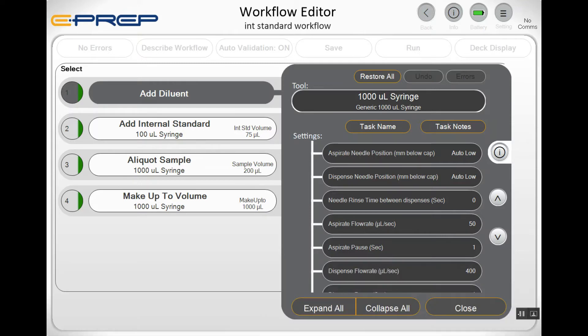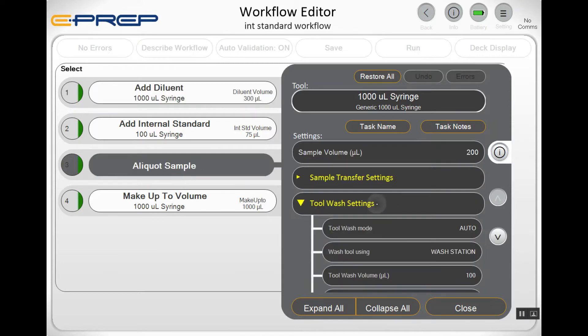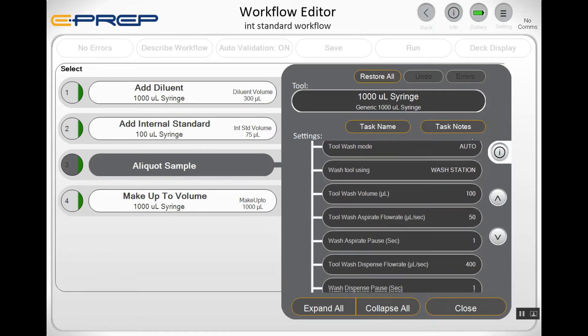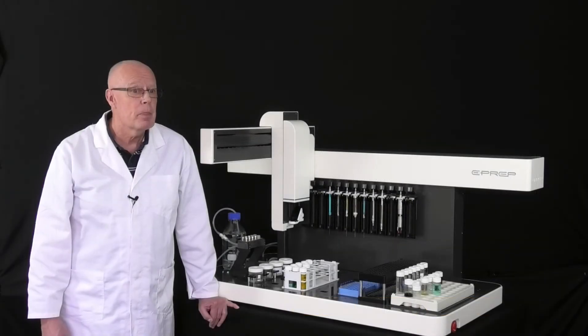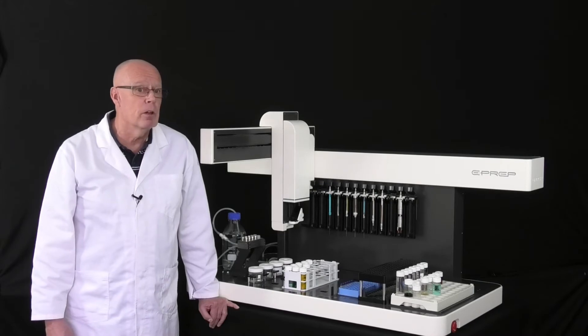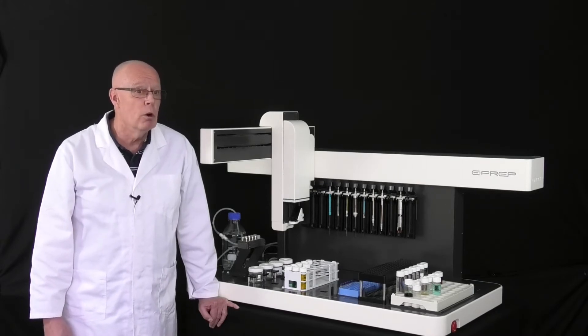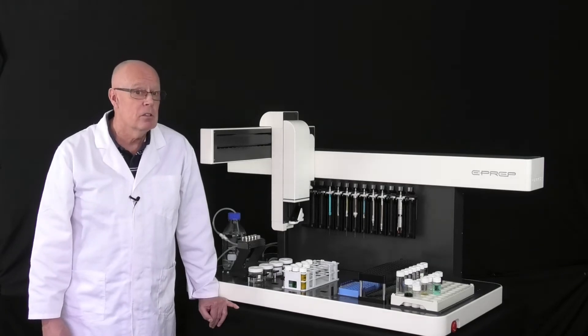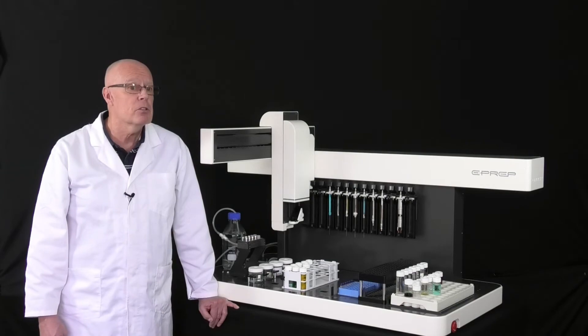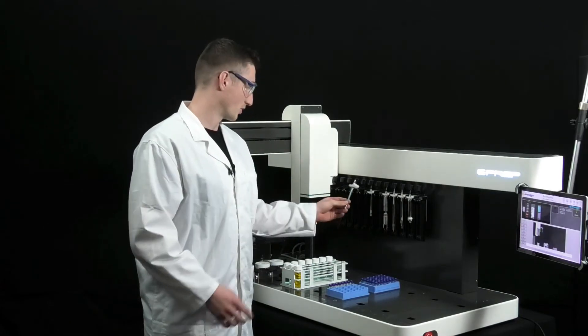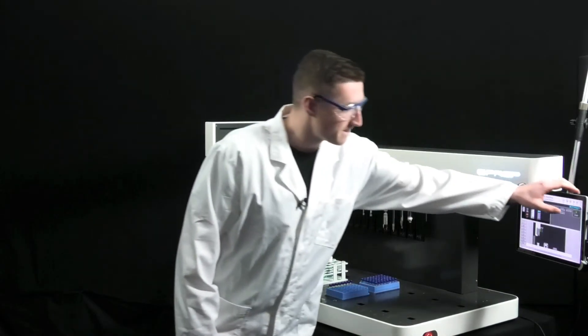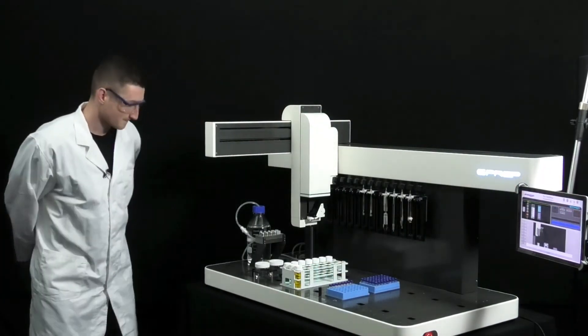Here's the good news: we've added default values to all these tasks, so you don't need to worry about them. But if you want to change something, you can. For example, you might have some particularly dirty samples that require different filtering or more syringe washing between samples — that's okay, these parameters can easily be changed. The experienced analyst creates the E-PREP workflow, and this is a one-off. Running the workflow, though, shouldn't require the skills of the experienced analyst, and it doesn't. The software has also been designed for easy execution: you set the number of samples, check all the syringes and containers that they're in the right place, and then start the workflow. That will keep the lab manager happy.